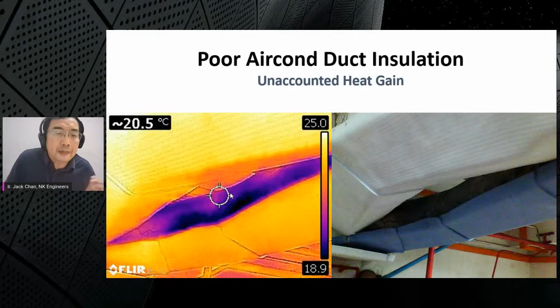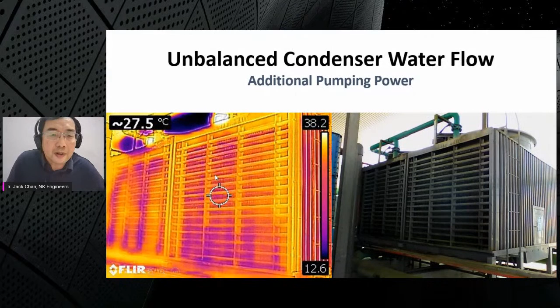All the way until the cooling tower, make sure that everything is balanced. The heat here should be almost the same color. If some areas have more water flowing down than the rest, this will affect the efficiency of your tower, so make sure everything is performing to the correct specifications.